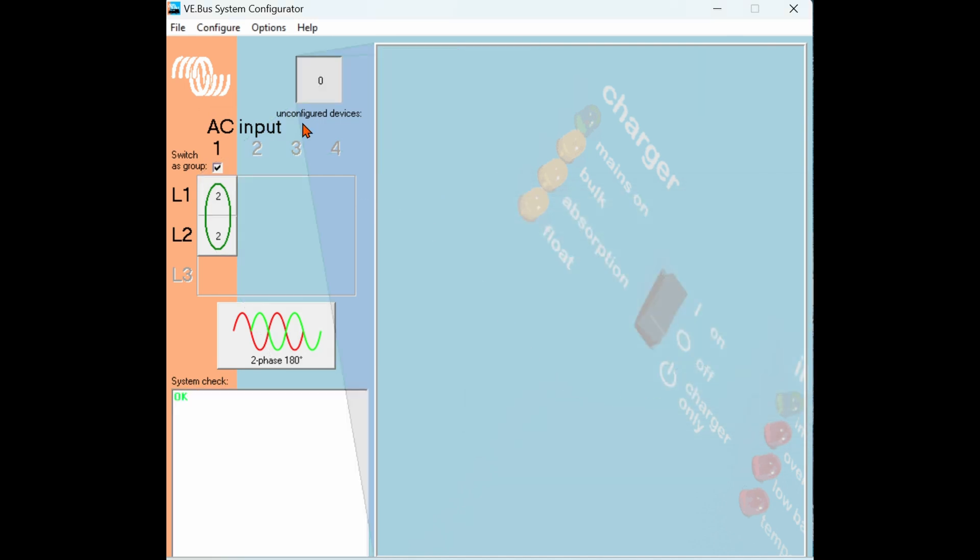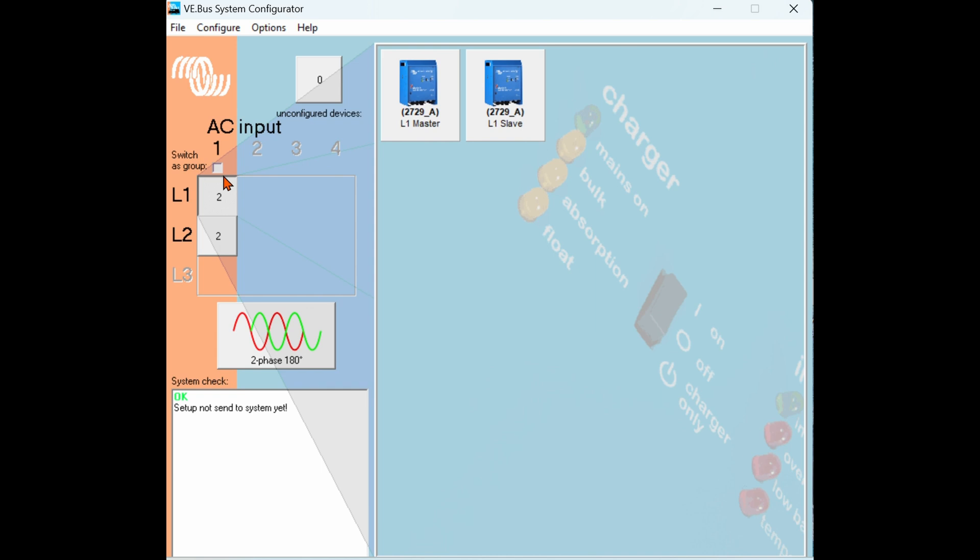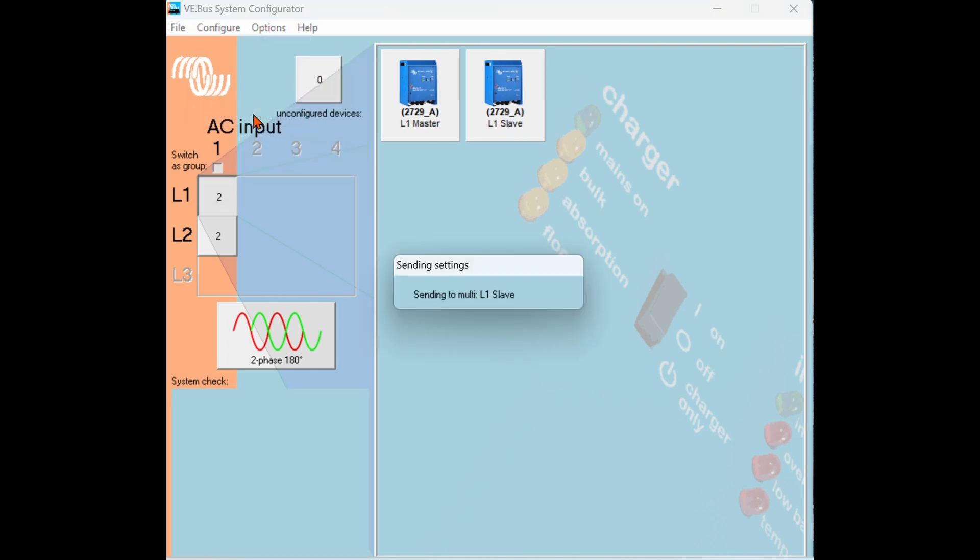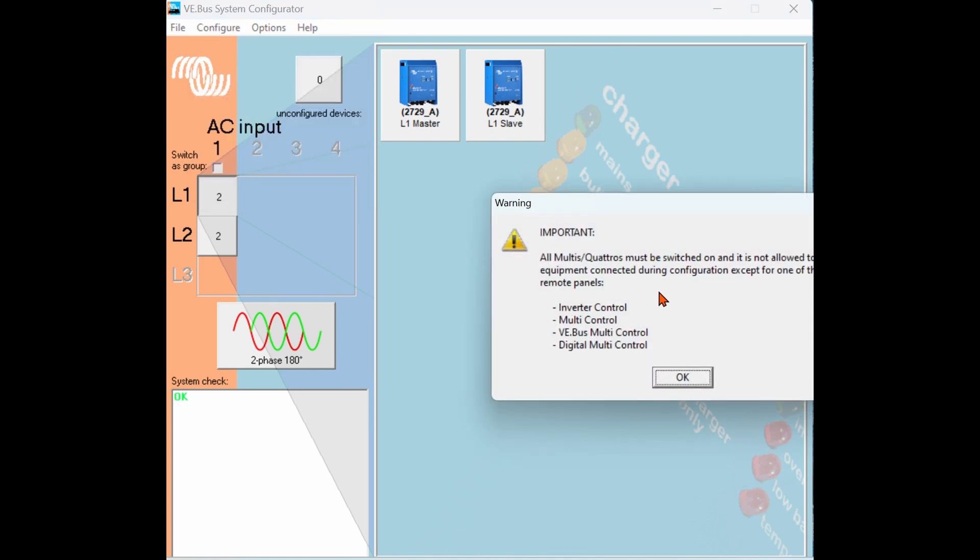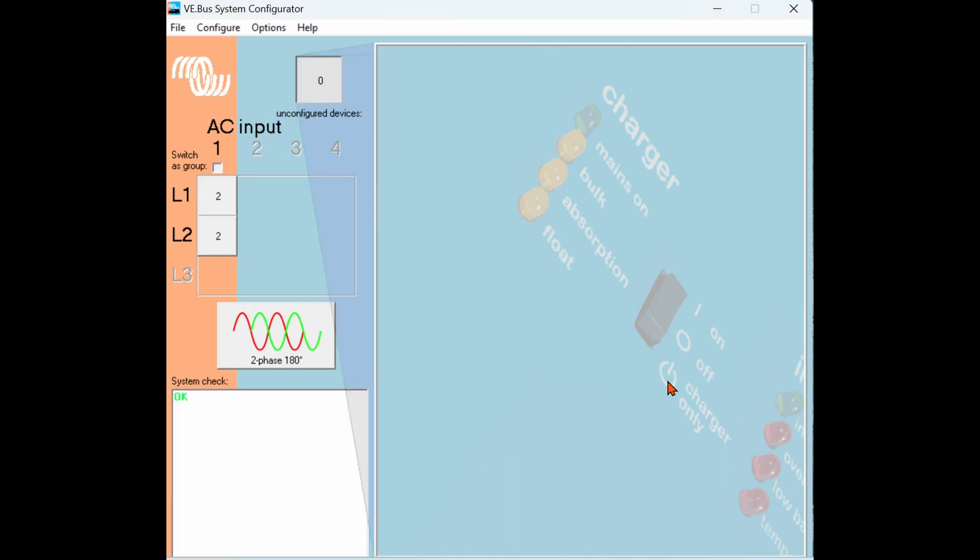As you can see here because the system is pre-programmed there are no unconfigured devices and when you click on each phase you can see the programmed inverters. Up above here is a very important box. This is called switch as group. This allows a 240 volt inverter system to accept a 120 volt input or a three phase to accept two phases. So in this case we're going to uncheck that and we're going to send configuration to send that change. Now that the system configuration is complete the last step is to program each individual inverter for function such as battery type and charging parameters.